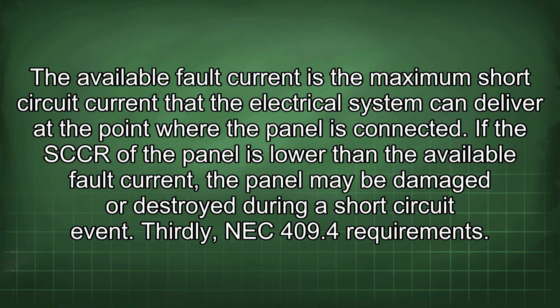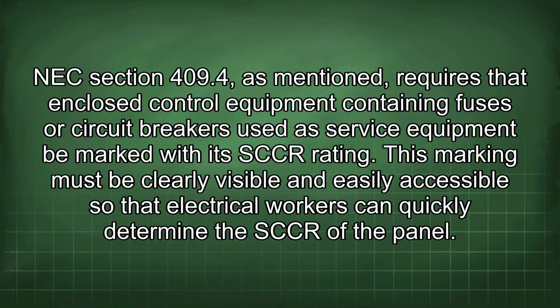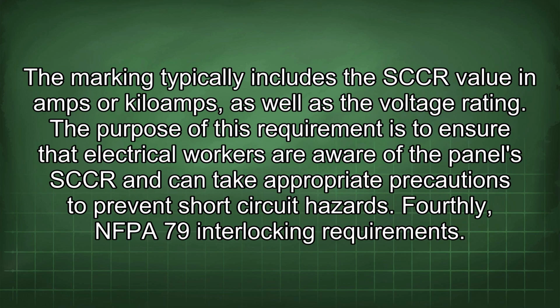Thirdly, NEC 409.4 requirements. NEC section 409.4, as mentioned, requires that enclosed control equipment containing fuses or circuit breakers used as service equipment be marked with its SCCR rating. This marking must be clearly visible and easily accessible so that electrical workers can quickly determine the SCCR of the panel. The marking typically includes the SCCR value in amps or kiloamps, as well as the voltage rating. The purpose of this requirement is to ensure that electrical workers are aware of the panel's SCCR and can take appropriate precautions to prevent short-circuit hazards.